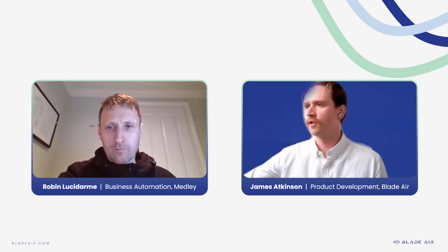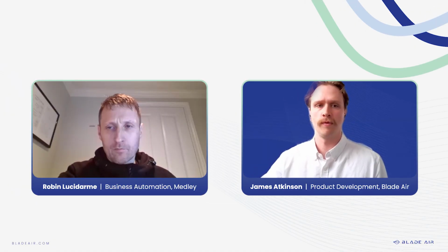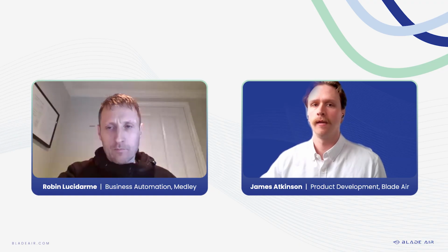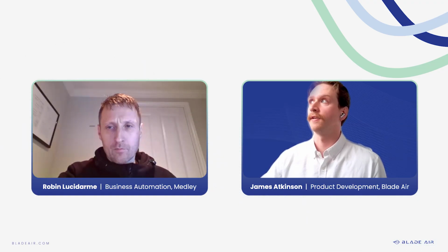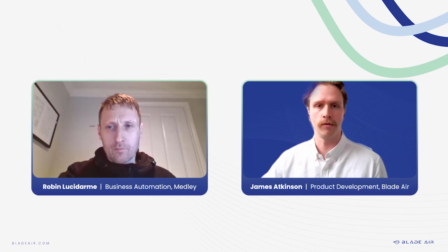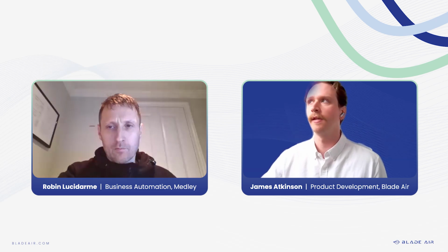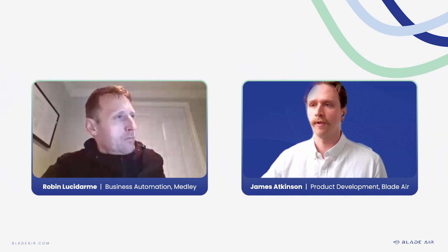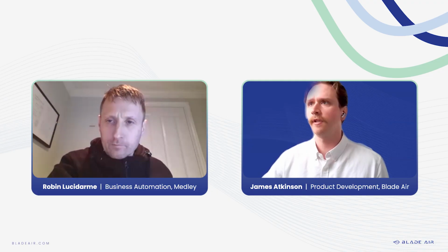What is the final pressure drop of the filter? That really depends on your system. We don't go over an inch. Usually it's about half an inch to 3/4 of an inch, but I will say 3/4 of an inch is a very conservative estimate because we have 8 times the dust loading capacity of a typical MERV 8 pleated filter to the same final pressure drop, right? So if you're getting 0.75 inches of water column across one of these, you will have almost a kilogram of dust in the filter. So typically we would replace over time instead of final pressure drop because they are low pressure. So it's not a pre-filter. This is a complete replacement, right?